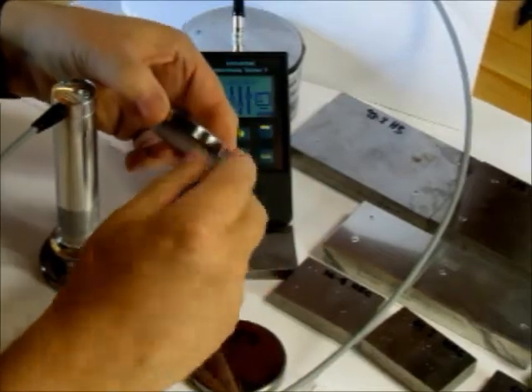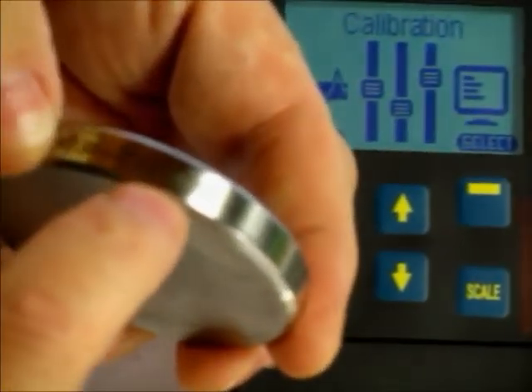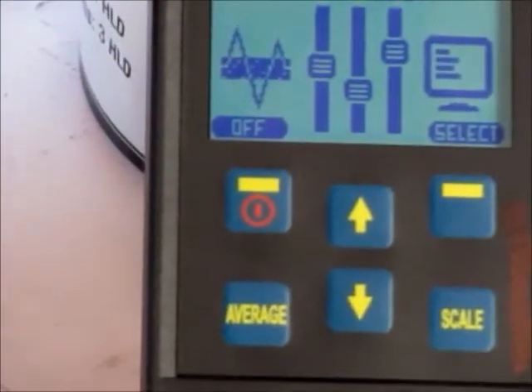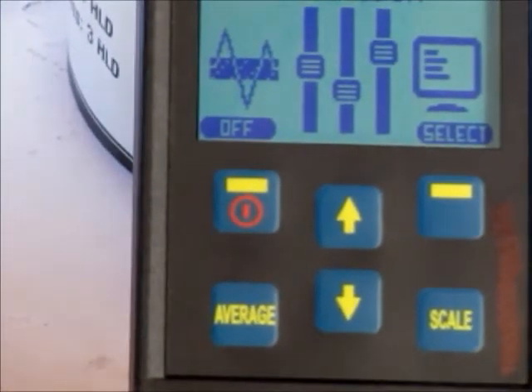Now with calibration test blocks, on the side of these blocks it will show you the test value. This is this 47.3, and then it's plus or minus 1 HRC, so very accurate, but we do have an error in the test block, of course, based on the hardness or the mean across. And with these test blocks comes the NIST calibration certificate.